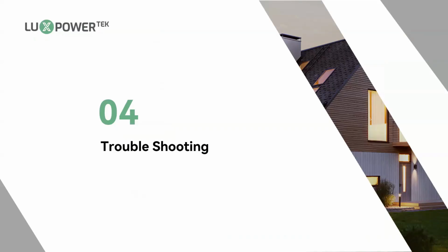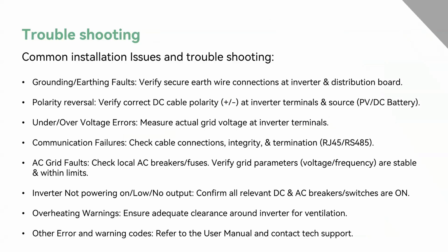There are some common installation issues we have come across before. For example, the first one, the grounding earth fault. If the grounding or earthing has some faults, we have to verify secure earth wire connections at the inverter and the distribution boards. For polarity reversal, we have to verify the DC cable polarity at the inverter terminals and the source, the PV and the DC batteries. For under or over voltage errors, we have to measure the actual grid voltage at the inverter terminals. Also check if we have chosen the right grid type.